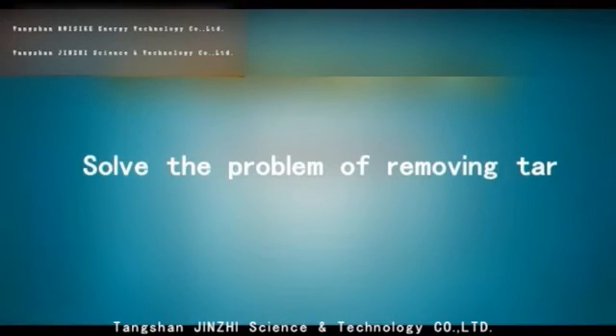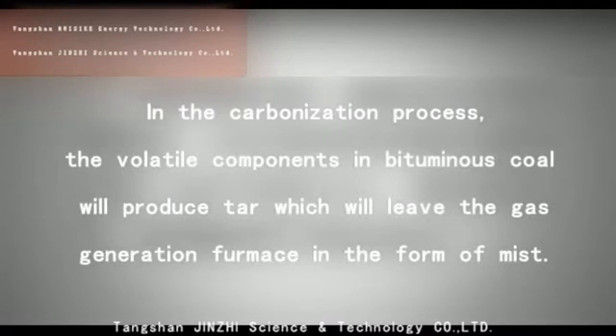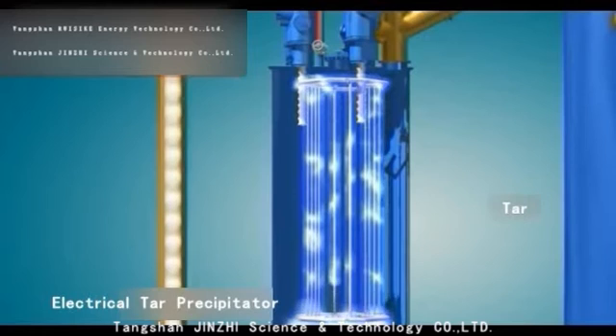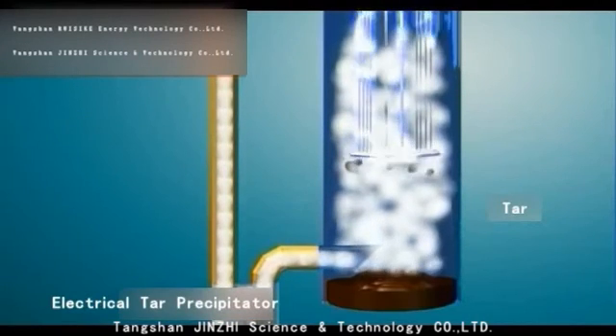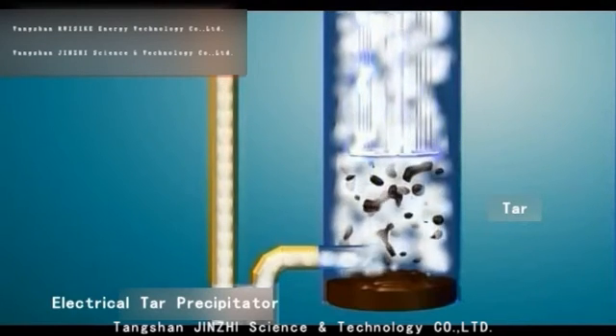The carbonization problem: in the carbonization process, the volatile components of bituminous coal will produce tar which leaves the gas generation furnace in the form of mist. During primary gas cooling, high boiling point tar can be condensed and removed, but the low boiling point light tar will still remain in the gas and it is difficult to remove by ordinary water washing. De-tar machines commonly used in the past have been gradually phased out because power consumption is high, efficiency is low, and management is complex. The electrical tar precipitator makes the tar in the gas atomized and perform directional movement under high voltage static electricity to achieve tar removal. It is highly effective with low power consumption and high tar removal up to 95–99%. The removed tar can be used as chemical raw materials, turning waste into treasure to solve the tar removal problem.